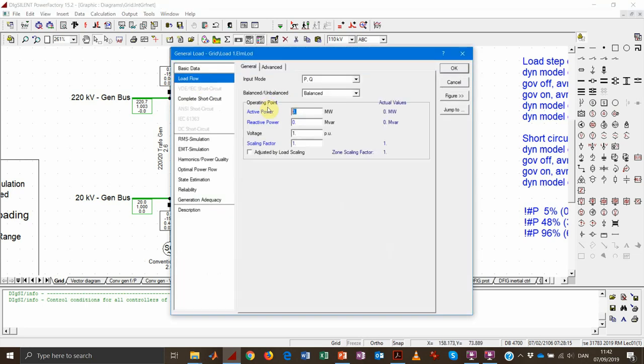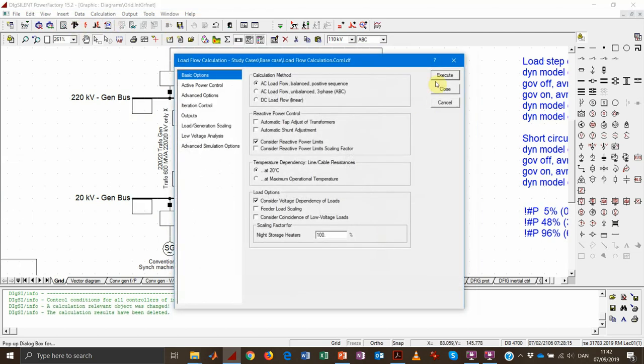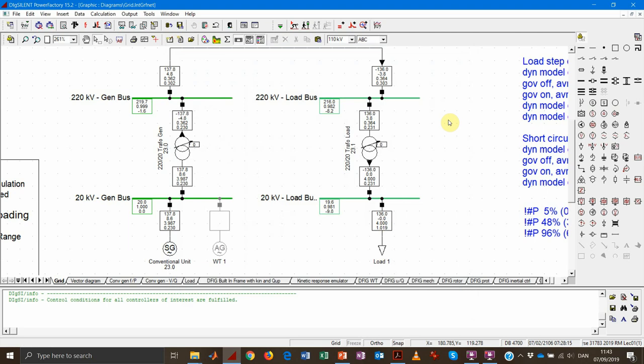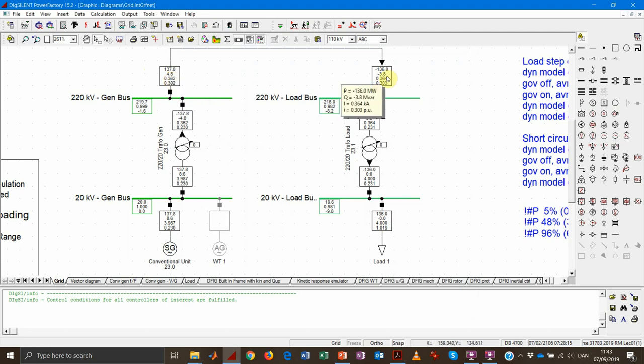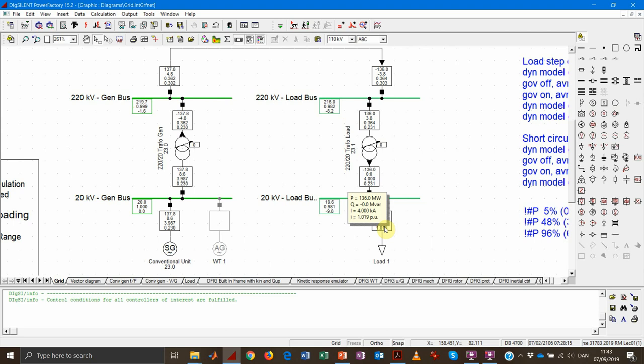Let's set the load to the SIL value of 136 megawatt. You will see that the line is almost neutral in terms of reactive power — it is absorbing 4.8 MVAR at one end and releasing 3.8 MVAR at the other, consuming about one MVAR net. It's not exactly zero because the SIL calculation assumes a lossless line with zero resistance and voltages at both ends equal to one per unit. If you remove the resistance and enforce those conditions, the actual SIL is 135.6 megawatt, and the line becomes transparent in terms of reactive power — purely active.